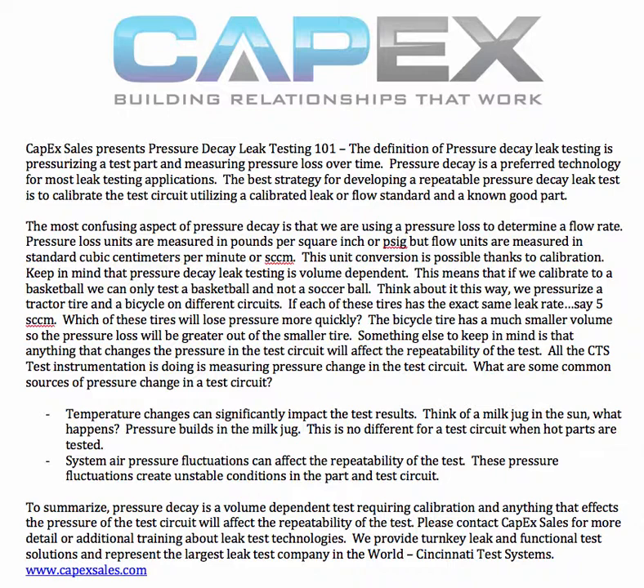Something else to keep in mind is that anything that affects the pressure in the test circuit is going to affect the repeatability of the test. All that the CTS instrument is doing is measuring pressure change in the test circuit. So anything that affects the pressure of the test circuit is going to affect the results of the leak test. It'll totally affect the repeatability. Always have to keep that in mind.